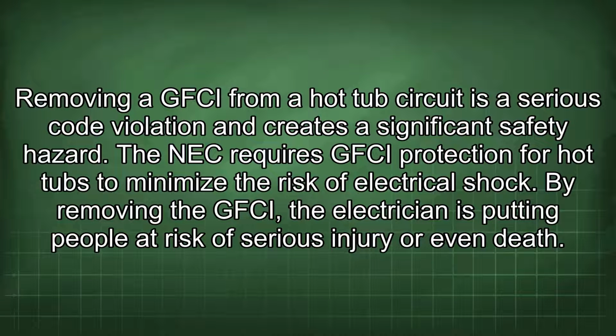Removing a GFCI from a hot tub circuit is a serious code violation and creates a significant safety hazard. The NEC requires GFCI protection for hot tubs to minimize the risk of electrical shock. By removing the GFCI, the electrician is putting people at risk of serious injury or even death.